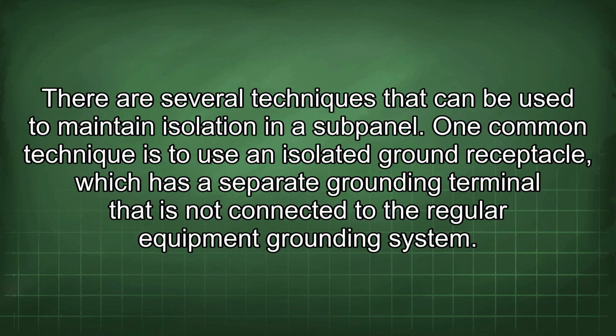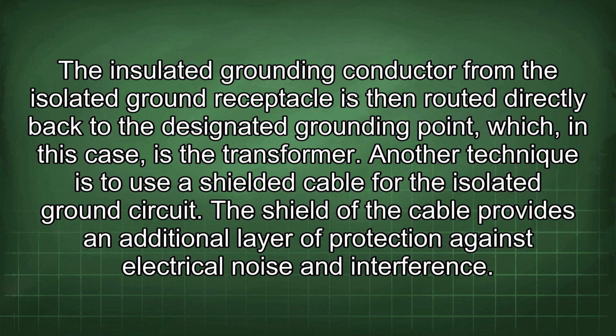There are several techniques that can be used to maintain isolation in a subpanel. One common technique is to use an isolated ground receptacle, which has a separate grounding terminal that is not connected to the regular equipment grounding system. The insulated grounding conductor from the isolated ground receptacle is then routed directly back to the designated grounding point, which, in this case, is the transformer.